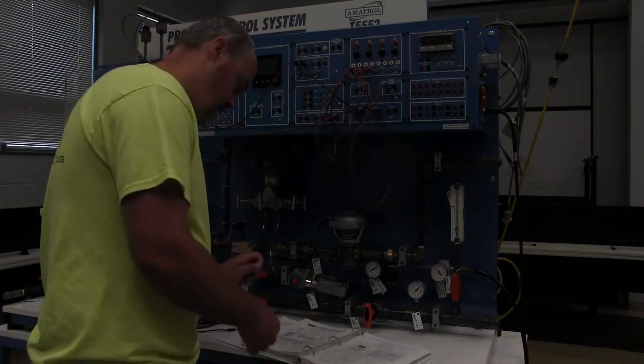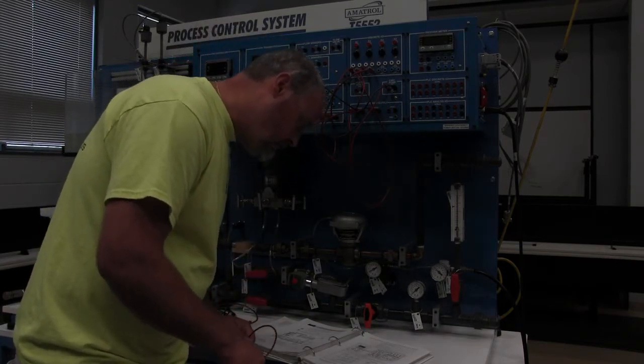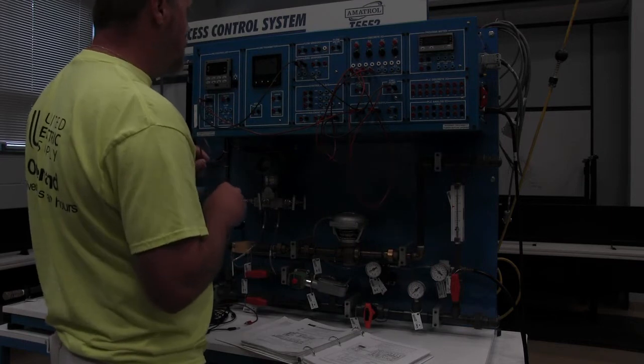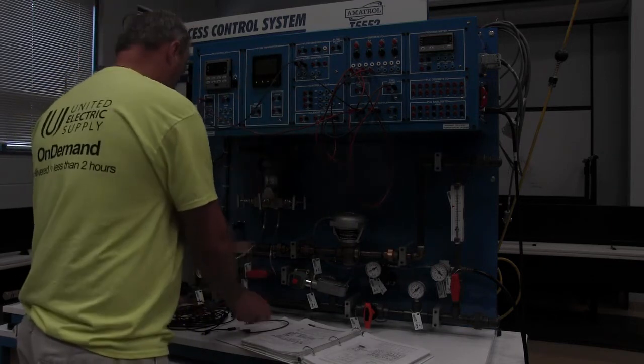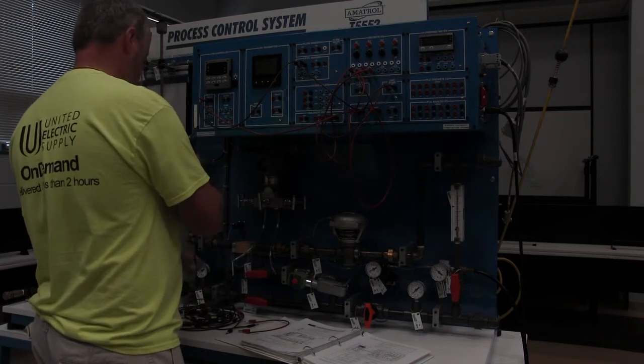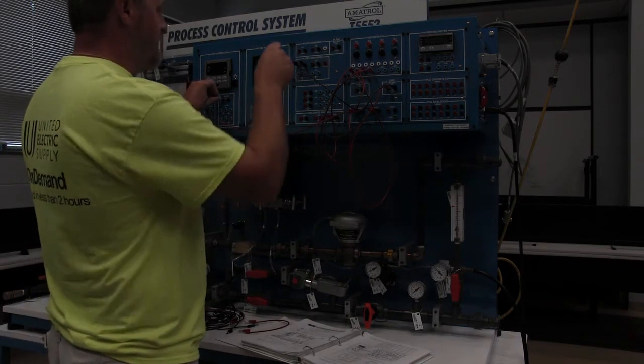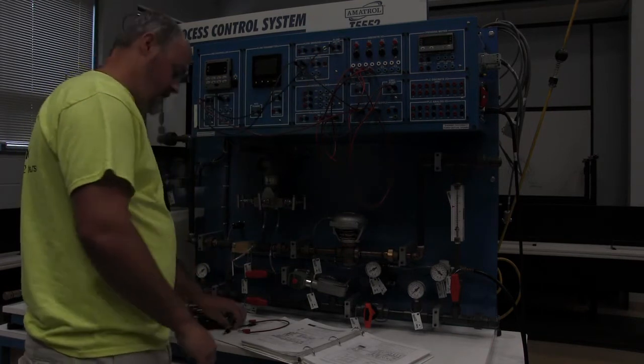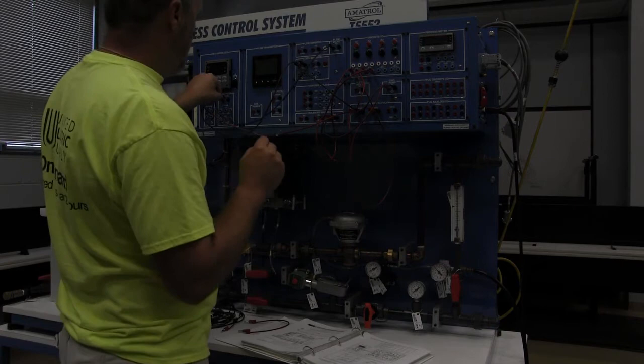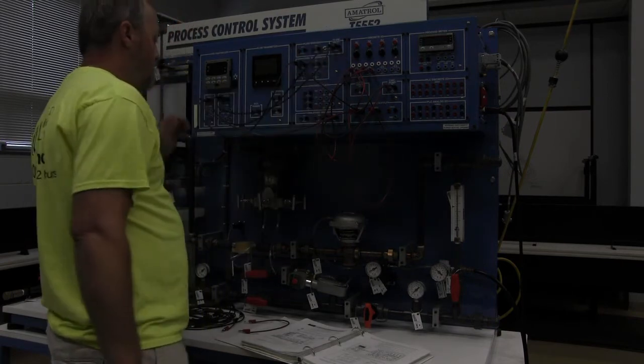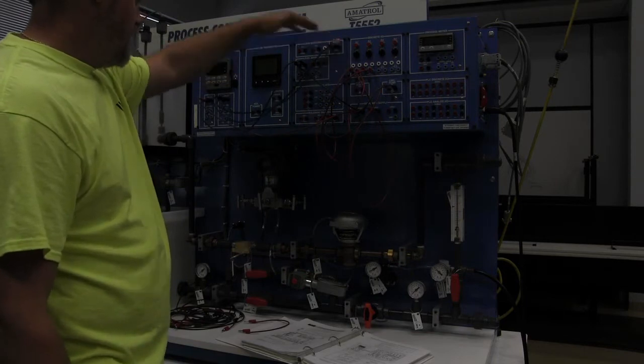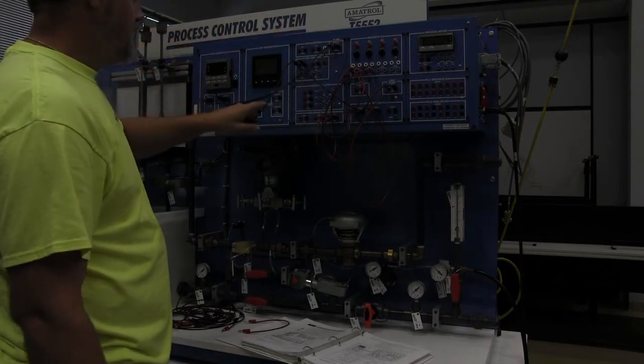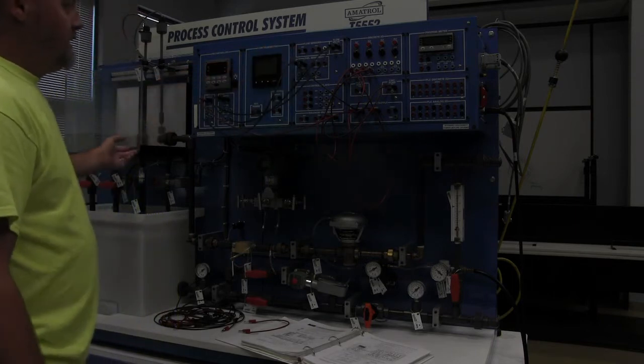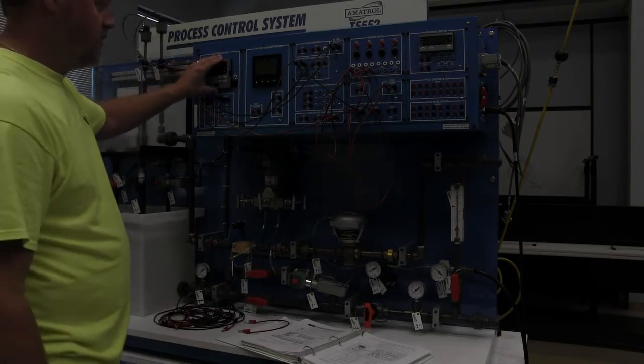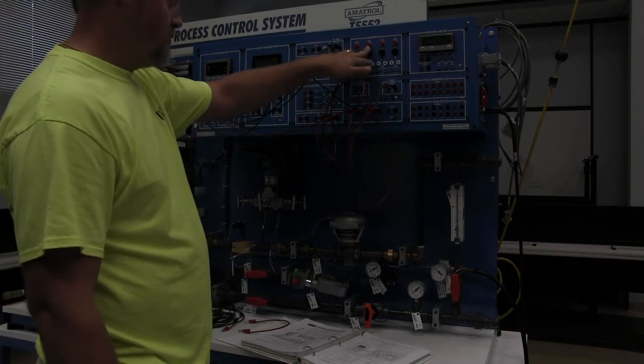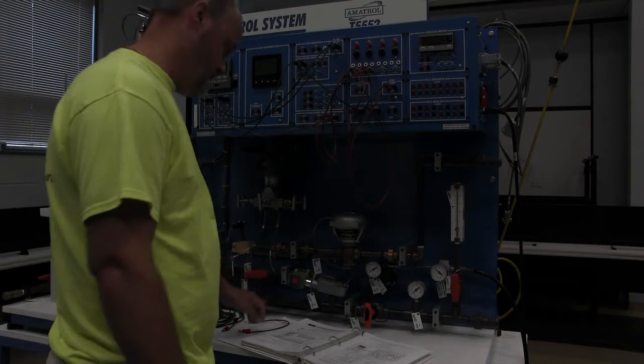So then we're going to need to take the analog out of the controller and go to flow valve. So analog out and flow valve 1. Need something a little bit longer for that. And again, it doesn't really matter what colors we're using right now. There is an industry standard when you're wiring stuff in the field. So we've taken the output to the flow valve, and we've taken the level transmitter to the input of the controller, and then we just have one switch hooked to a solenoid valve and the other switch hooked to the circulator pump.